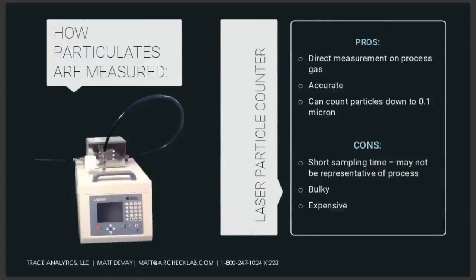So particles. One of the most common and robust ways to measure particles are laser particle counters, or LPCs. These measure your process gas directly while it is flowing with minimal interference. Basically, you hook it up, open the valve, turn it on, and you let it do its thing. They sample for a fixed amount of time, typically about a minute, but you can adjust that if you need to. Air will flow through the thing for a minute, it'll count for a minute, it'll turn off for a minute, then it'll count again for a minute, typically so on and so forth until you tell it to stop.